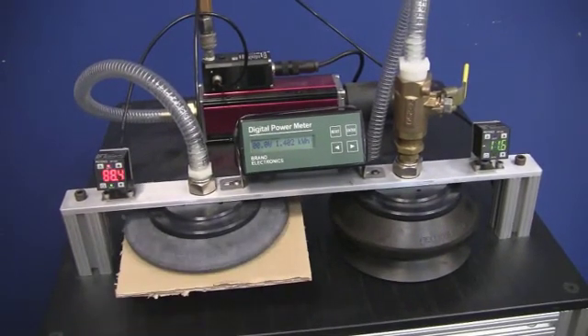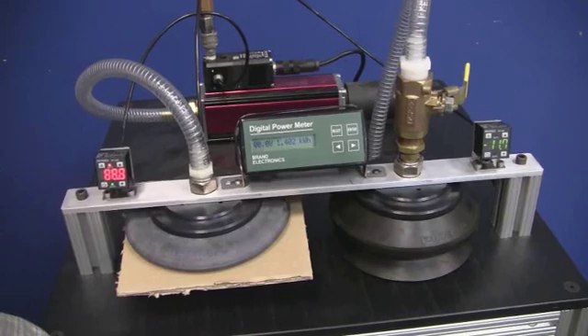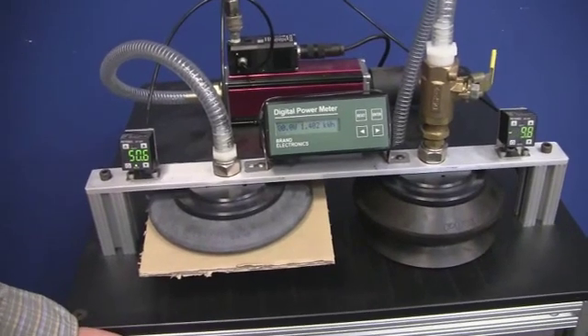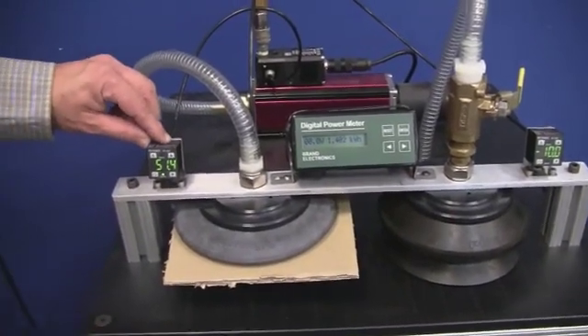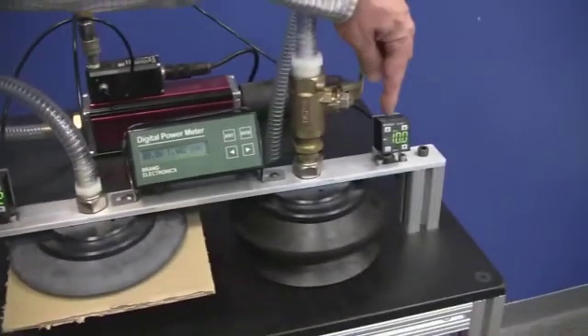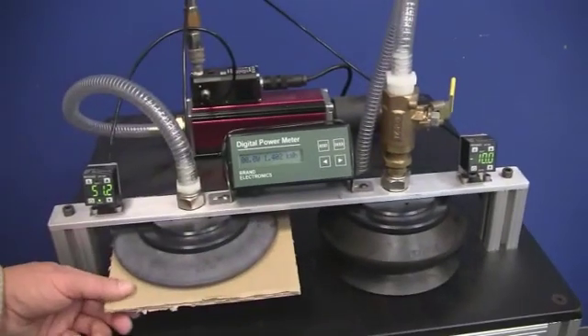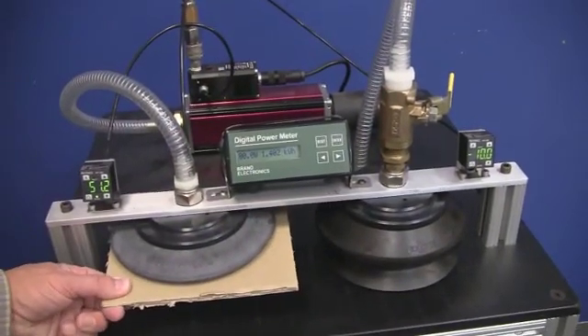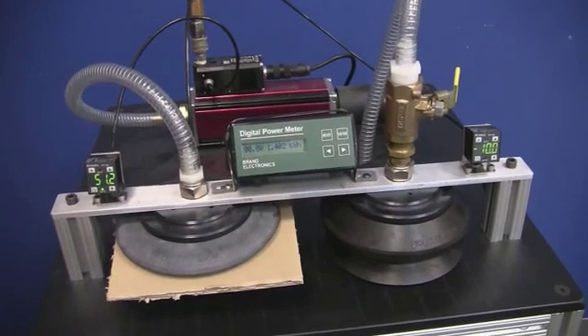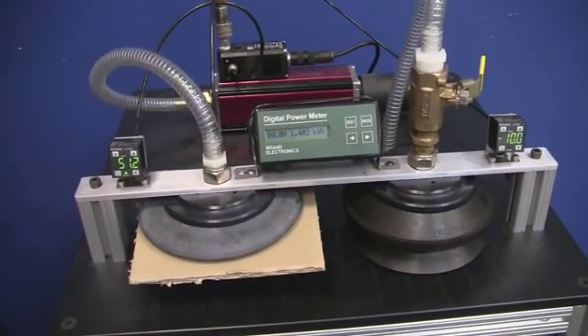When using compressed air, you can also adjust the supply pressure to the pump to help optimize its efficiency. The gauge here shows the supply pressure and by lowering it, it will affect the vacuum level as shown here, but you still can adjust it down so that you have a very safe handling system. Any time you can lower the supply pressure, the air consumption will be reduced.